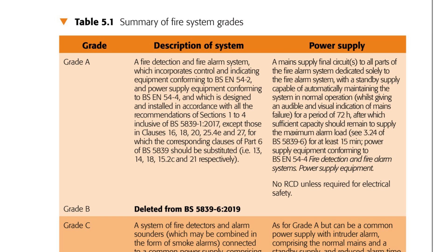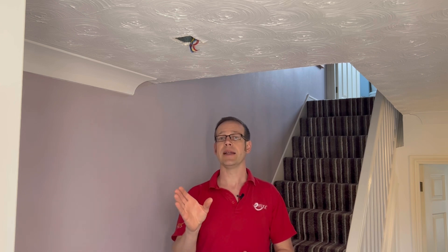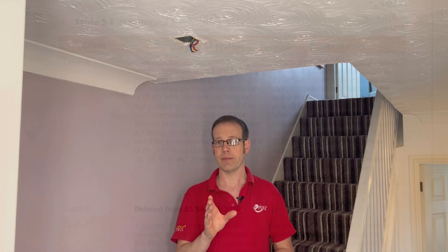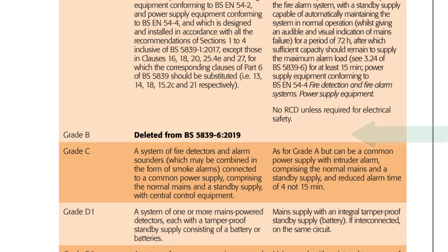The power supply to a Grade A alarm should only feed the fire alarm and nothing else, and the system should have a backup that can keep the alarm operable for at least 72 hours, after which sufficient capacity should remain to supply the maximum alarm load for at least 15 minutes. So if a detector was triggered at the very end of 72 hours of running on battery backup, the panel should still be able to sound all connected alarms for at least 15 minutes. It's also recommended that this grade of system has no RCD protecting the supply cable unless necessary for electrical safety.